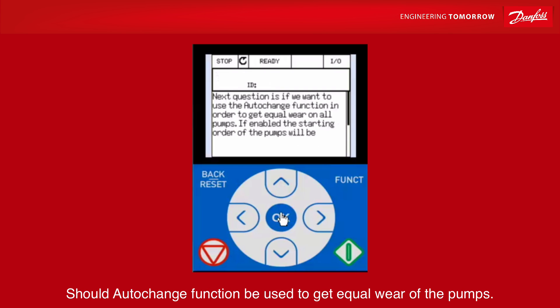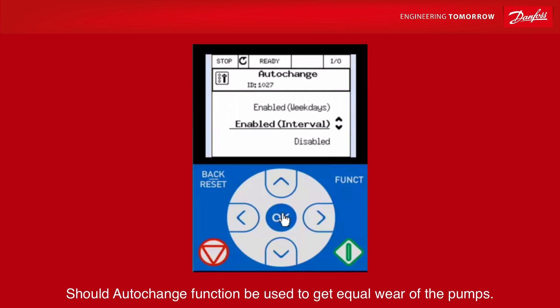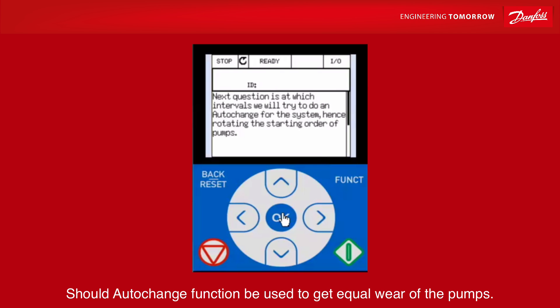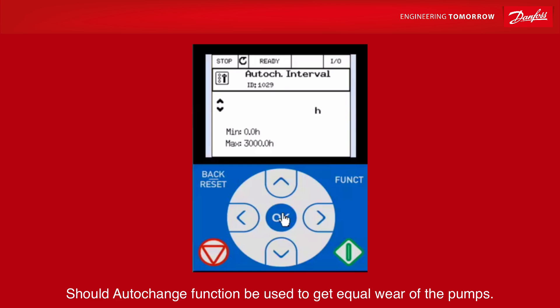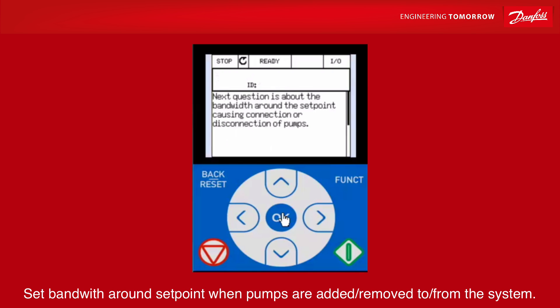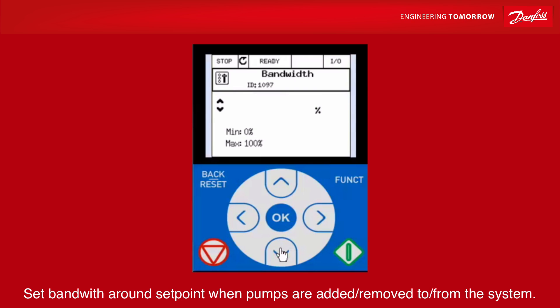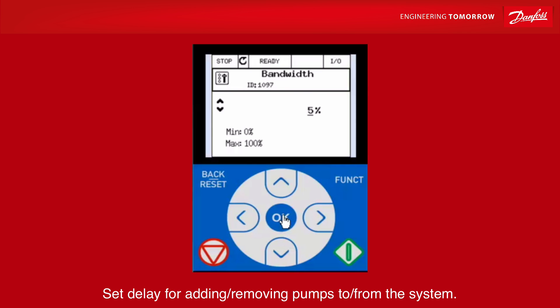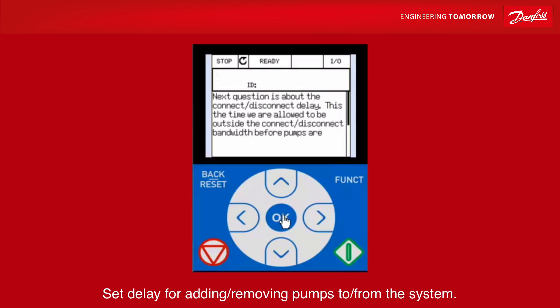Should auto change function be used to get equal wear of the pumps? Set bandwidth around set point when pumps are added or removed from the system. Set delay for adding or removing pumps to the system.